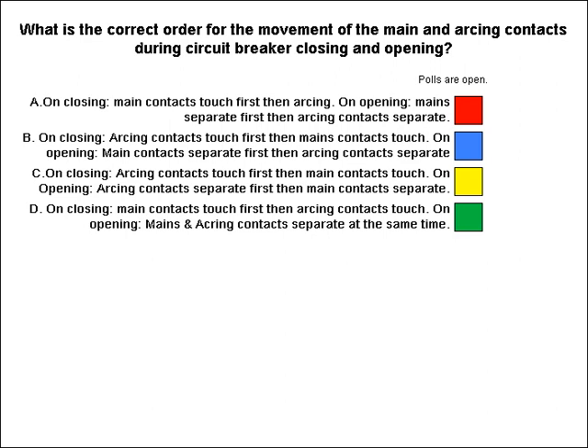What is the correct order for the movement of the main and arcing contacts during circuit breaker closing and opening? A. On closing, main contacts touch first, then arcing. On opening, main separate first, then arcing contacts separate. B. On closing, arcing contacts touch first, then main contacts touch. On opening, main contacts separate first, then arcing contacts separate. C. On closing, arcing contacts touch first, then main contacts touch. On opening, arcing contacts separate first, then main contacts separate. D. On closing, main contacts touch first, then arcing contacts touch. On opening, main and arcing contacts separate at the same time.